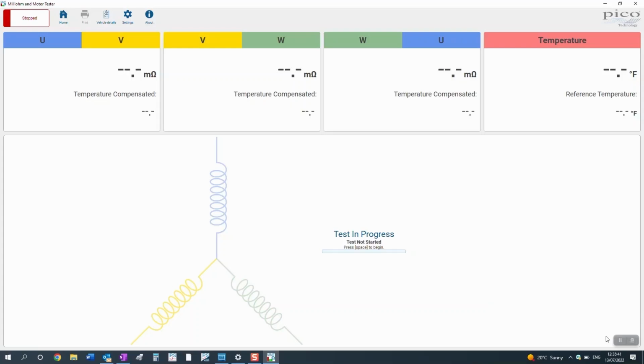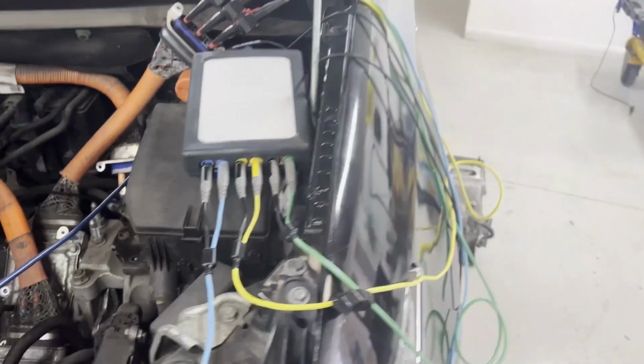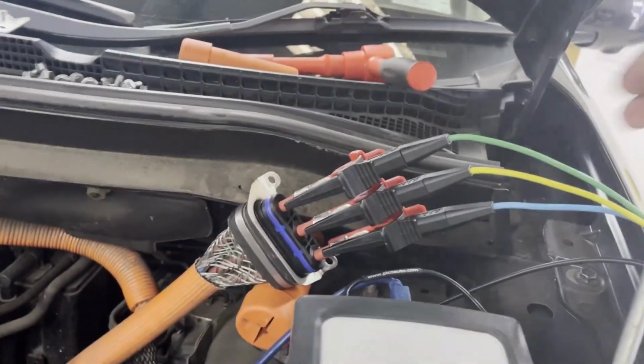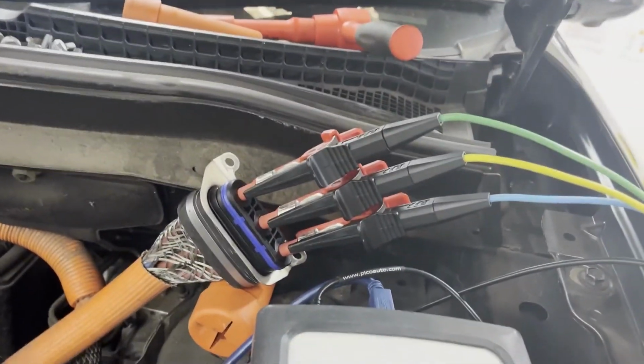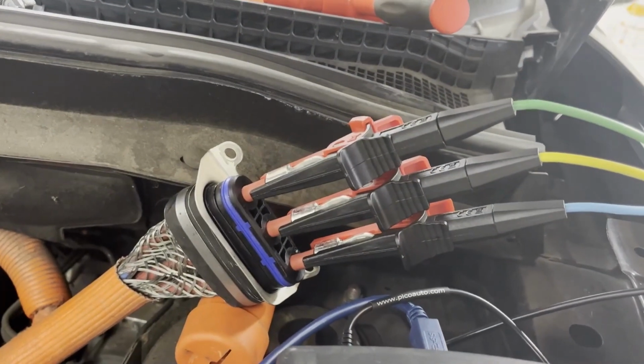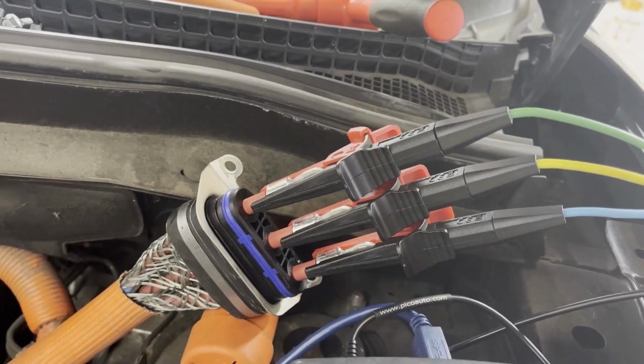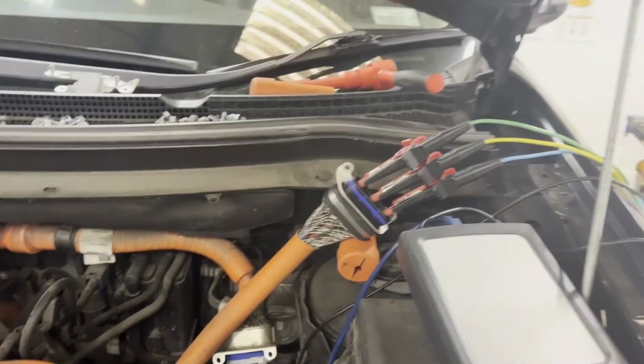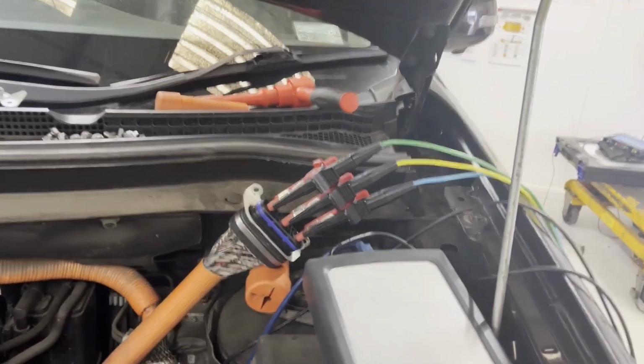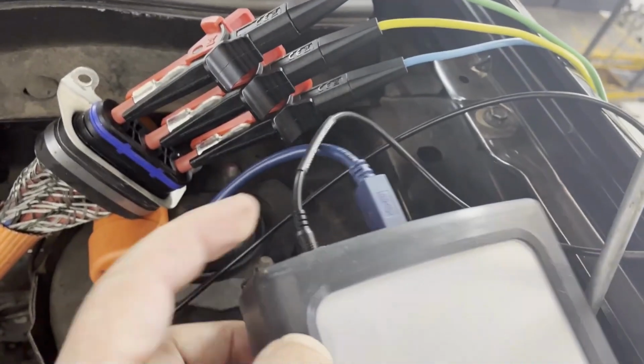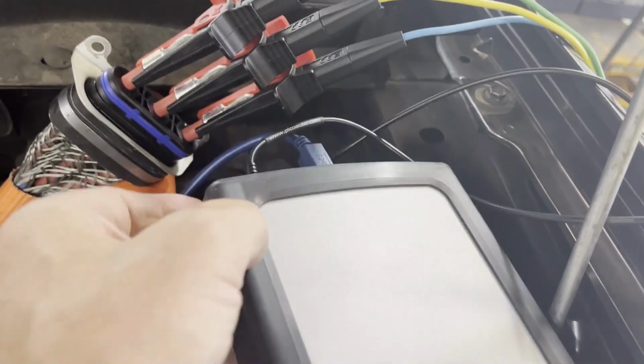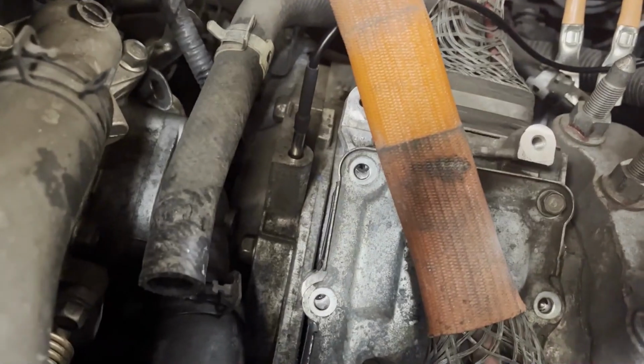And let's have a look at the connections. So six wires, and they attach to Kelvin clips because this is actually a six wire measurement. But we're going to measure each phase in one hit. So we're going to measure the resistance between UV, VW and WU. You'll notice in the back of the tester as well, there's an additional cable here. This is a temperature probe. And if we follow that down, that just rests on the transmission there. You can see that there.